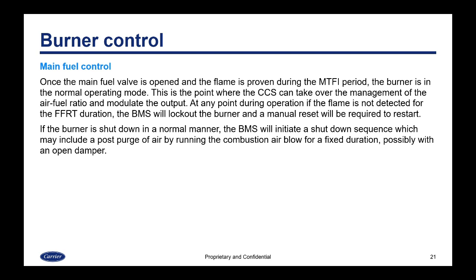At any point during operation, if the flame is not detected for the flame failure response time duration, the BMS will lock out the burner and a manual reset will be required to restart. If the burner is shut down in a normal manner, the BMS will initiate a shutdown sequence, which may include a post-purge of air by running the combustion air blower for a fixed duration, possibly with an open damper.